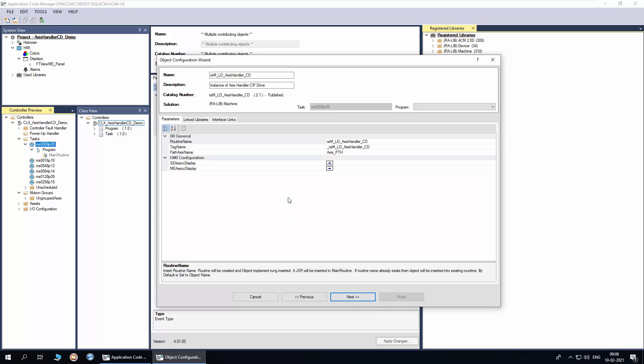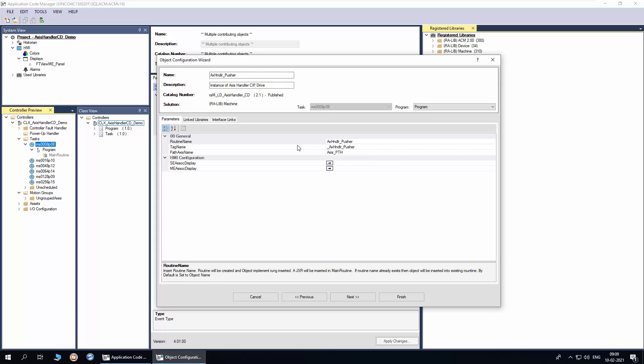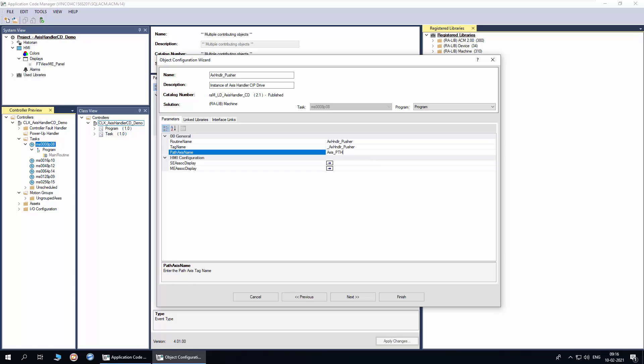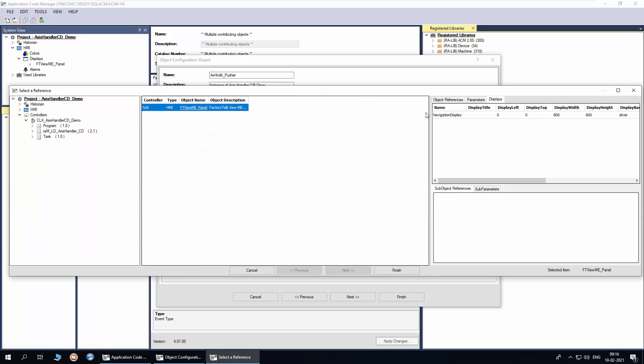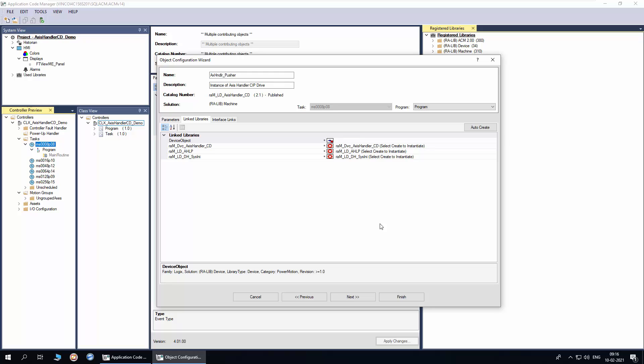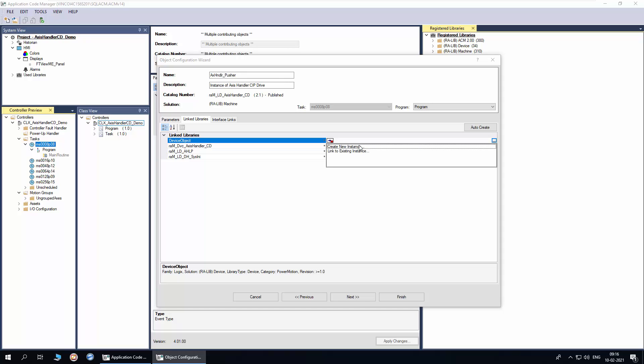I will name the instance as axis handler pusher. Select the program where the object is to be instantiated. I will select the program already created, or you can add a new program. The routine name and tag name are derived from the object instance name and can be modified if required. This is the path axis name — I will modify the name as axis pusher path. Select the display where the navigation object is to be placed and click next. In the link libraries, I will first create the device object. To create, click on create new instance.